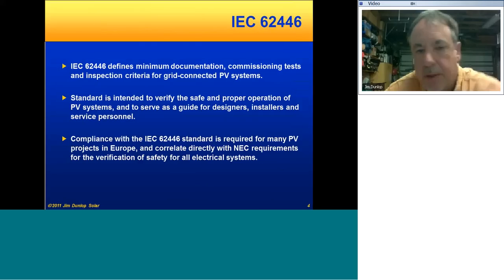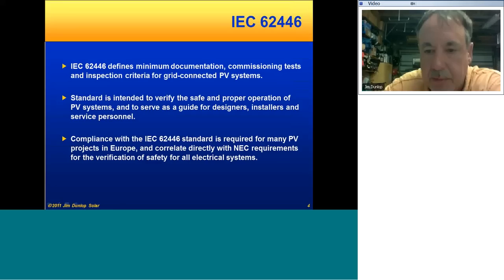One of the things that is the basis for this system documentation and commissioning is the IEC 62446 standard. That's a fairly new standard developed by some guys in the UK, and it's required for many of the incentive programs in the UK and in Europe generally, that these tests are done and the documentation is submitted in compliance with this standard. Basically, it's to verify safety, and includes insulation resistance testing, voltage and current verifications on strings and so forth. It's not really performance verification so much as verifying functionality of the system, with voltages and so forth within 5% of nominal expectations at steady sunlight and temperature levels. I recommend everyone get a hold of this standard eventually. This is becoming a commonplace expectation with larger projects, certainly.